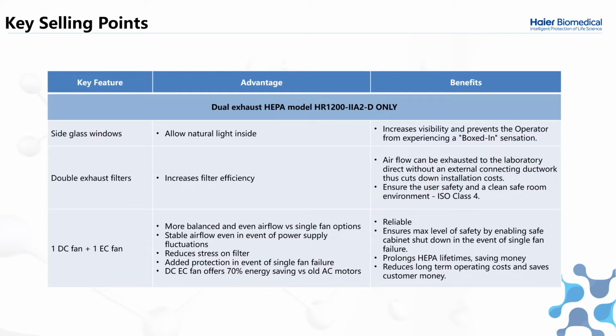With the dual HEPA, there's a slightly different fan system: one DC fan and one EC fan, instead of 2 DC fans or 2 AC fans. While having 2 fans, if one fails, the other one can direct itself to protect the user, which is a great safety feature. The airflow is more balanced and stable, and it reduces the stress on the filter as you have 2 smaller fans. The EC fan can also scale up and scale down depending on how much power it needs to use. These are great for reliability, they extend the life of the HEPA filter, and in general they can reduce the long-term operating cost to the customer.